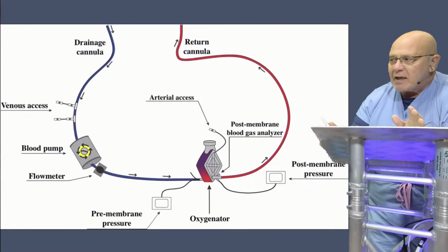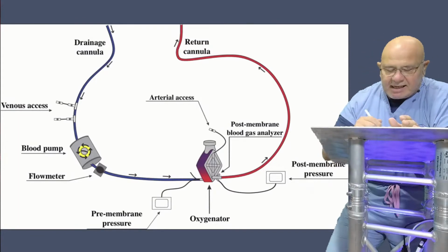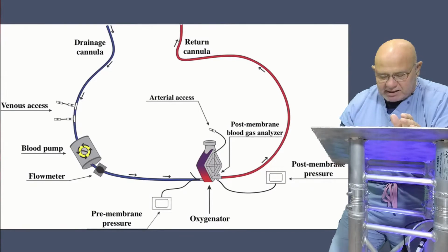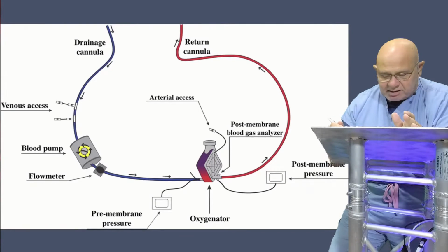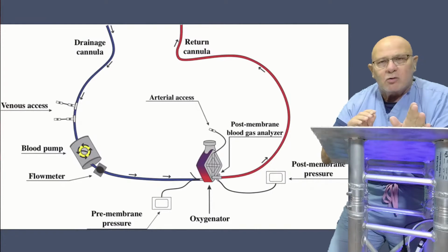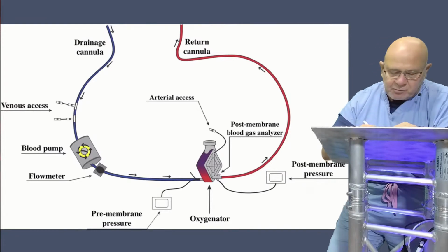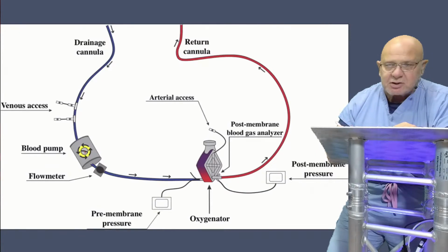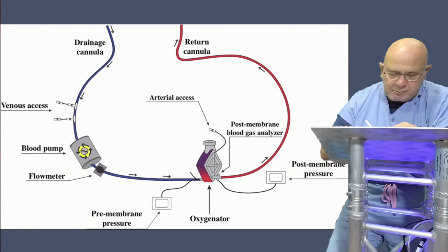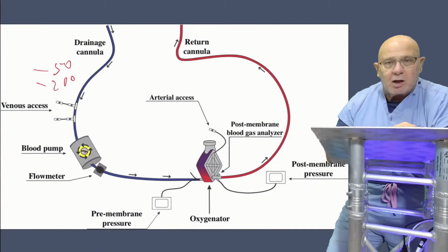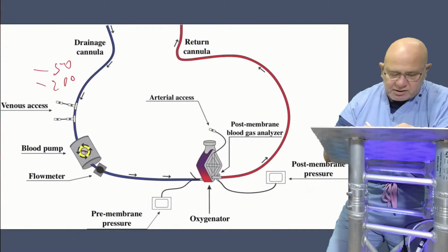So here you have a basic ECMO circuit, and it has a CRRT. I'm going to connect a CRRT machine to it. Let me see if that's, yes, that's here. So here in this particular diagram, we're only looking at the ECMO circuit. Your drainage cannula here, so this is your blood pump, your centrifugal blood pump or your peristaltic pump, it doesn't make any difference which. This is going to be a negative number, and it can range anywhere from negative 50 all the way to negative 200, depending on the flow, size of the cannula, resistance to flow, all of those kinds of things. So you have the blood coming down here.